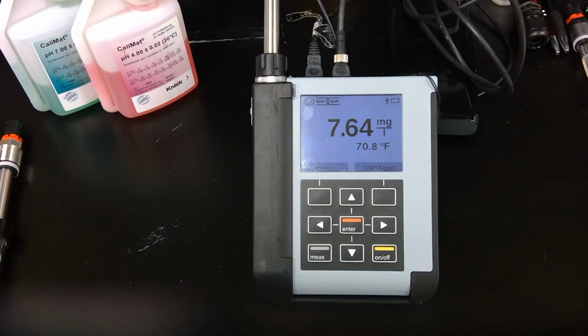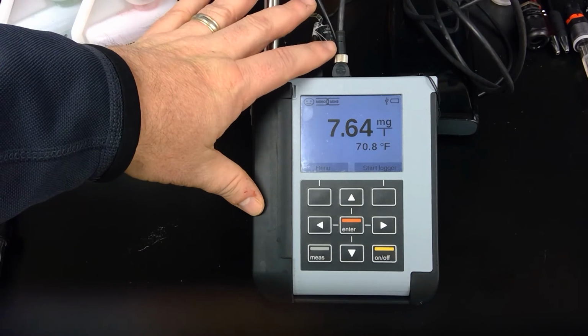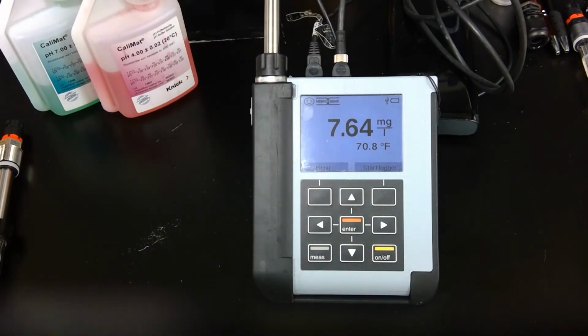Also, the other thing to remember is when we talked about the membrane replacement, at the end of the video, we talked about the importance of polarization. So whenever you go to do a calibration on an amperometric Clark cell type DO sensor, you need to make sure that the sensor has been polarized. We typically say minimum of 6 hours, and we also recommend that if you're going to do PMs where you're going to do calibrations, plug the DO probe into your Portavo, into your transmitter, whether that be an Evo, a multi, whatever it might be, and let it power up and stay powered overnight. So the next morning when you come in, the DO probe is already polarized. If you don't do that and you calibrate it and put it into the process or the application, it could drift. And then of course your measurement's not going to be accurate.